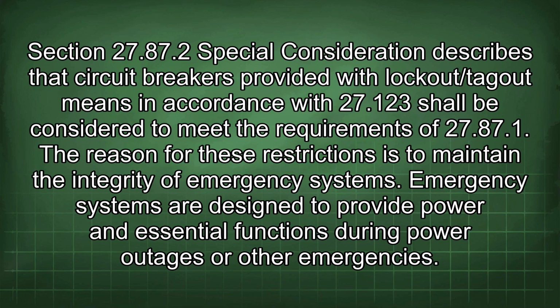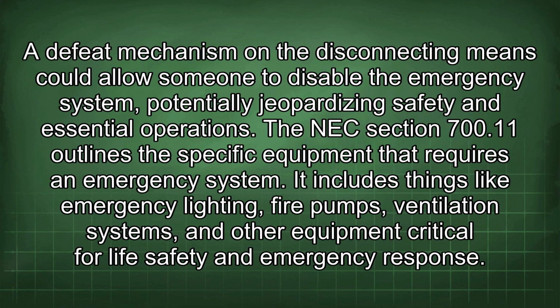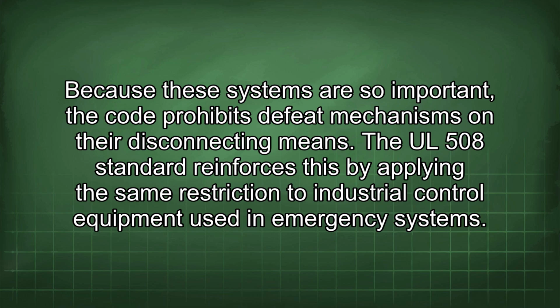Emergency systems are designed to provide power and essential functions during power outages or other emergencies. A defeat mechanism on the disconnecting means could allow someone to disable the emergency system, potentially jeopardizing safety and essential operations. The NEC Section 700.11 outlines the specific equipment that requires an emergency system. It includes things like emergency lighting, fire pumps, ventilation systems, and other equipment critical for life safety and emergency response. Because these systems are so important, the code prohibits defeat mechanisms on their disconnecting means.